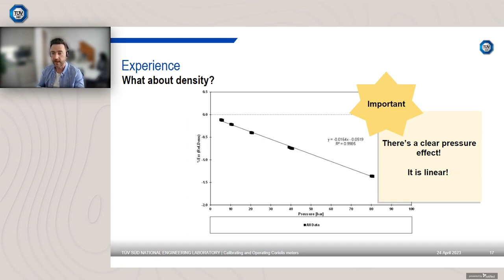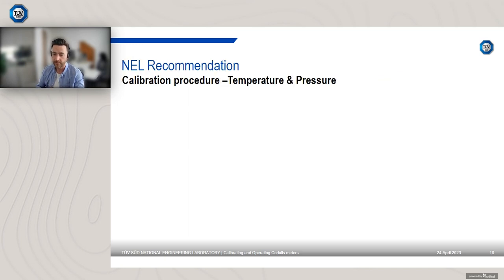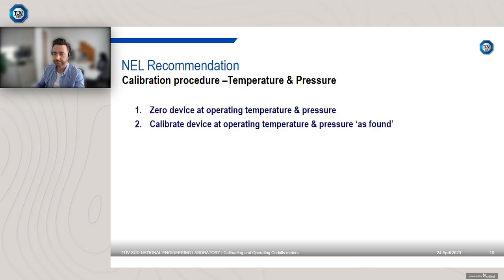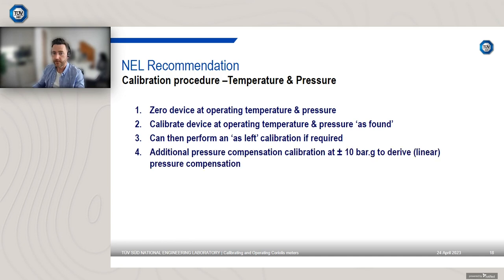So what we recommend is use a dynamic correction. So use a pressure transmitter that's monitoring the line pressure. You have that traceable compensation factor, and it calculates what the pressure compensation factor is with respect to the line pressure, and always uses a dynamic correction rather than a static correction. That's the optimum method, and that's what we recommend. Now, that's the NEL recommendation, and that also meets the NSTA, the North Sea Transition Authority regulations.